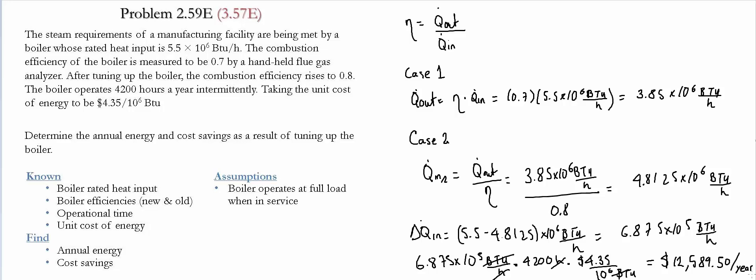So notice that to solve this problem, we were able to determine the rate of energy out, and it's exactly the same for the boiler before and after. We then calculated the energy in once it was tuned up, we calculated the difference between them, multiplied by how long it runs for and the cost, and that gives us the savings.